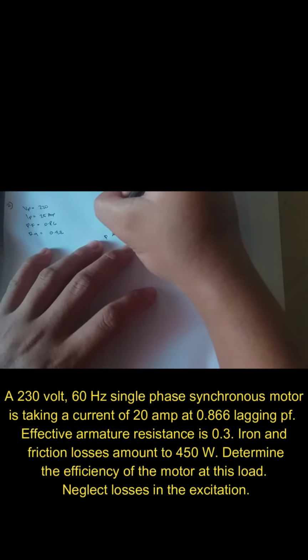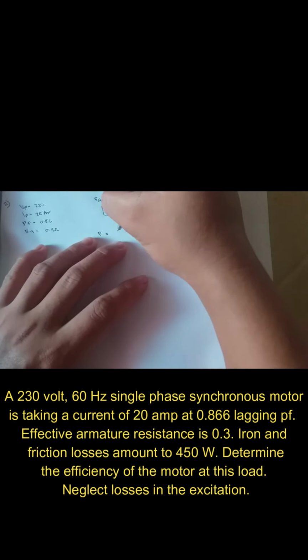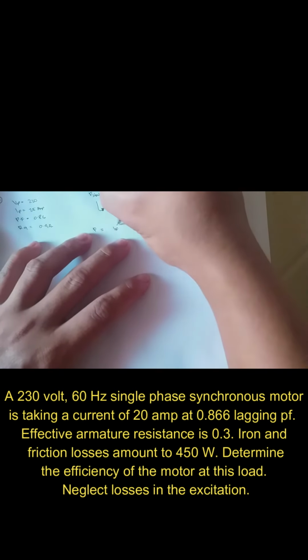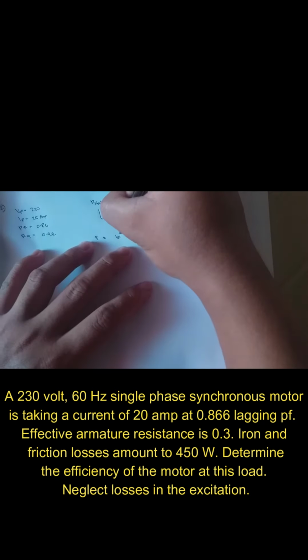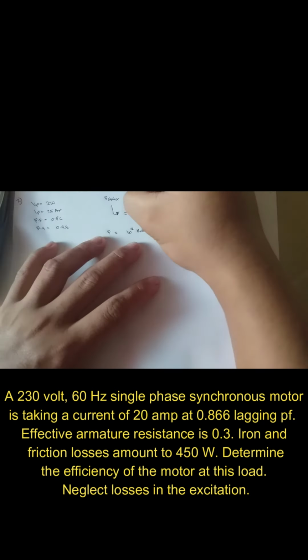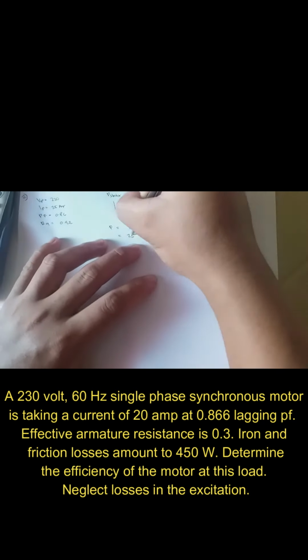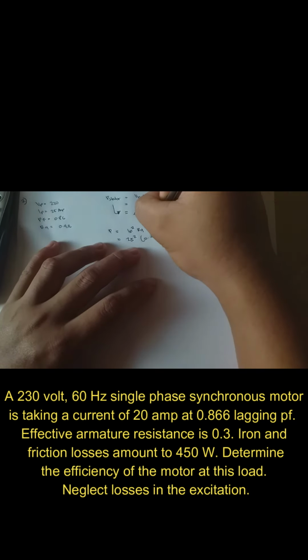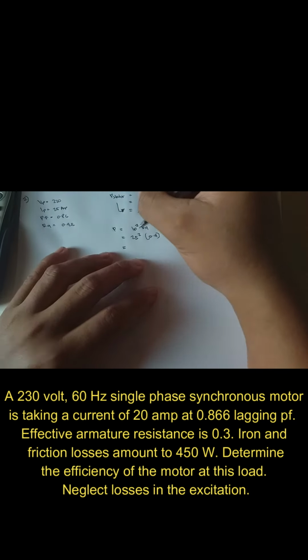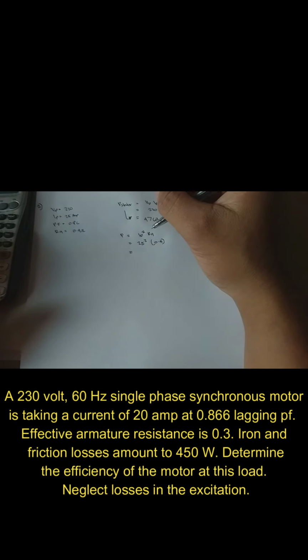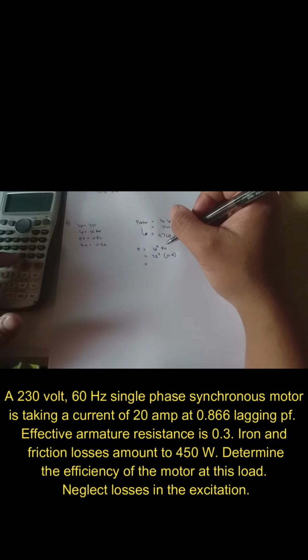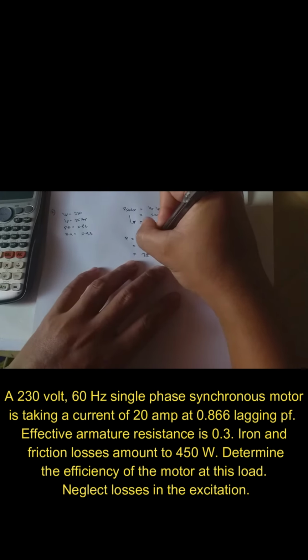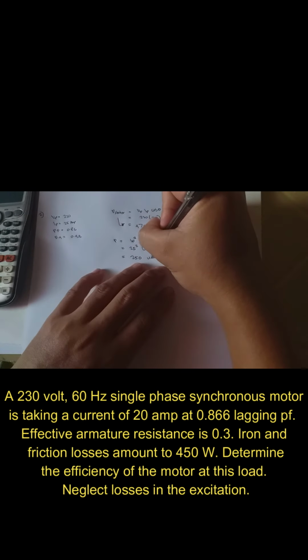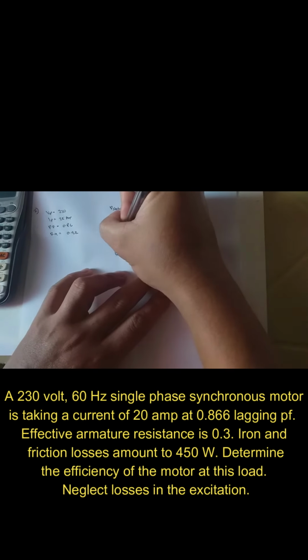So we can compute the copper loss, which is equal to I squared times Ra. 25 squared times 0.4, which is our resistance. So 25 squared times 0.4 is equal to 250 watts. That's our copper loss.